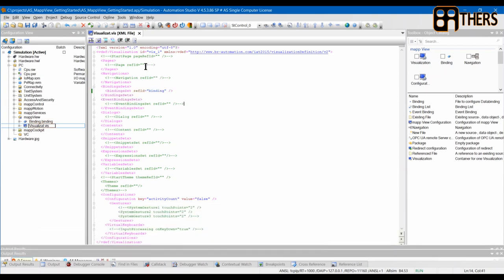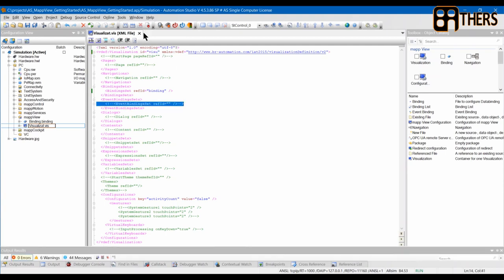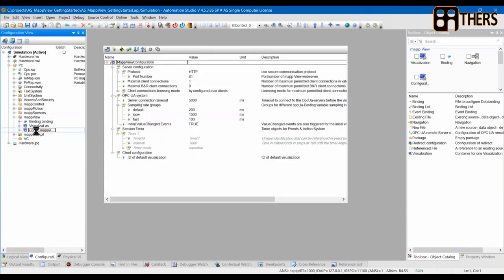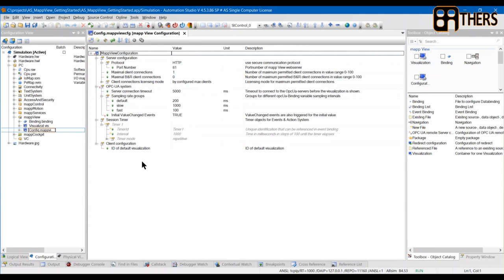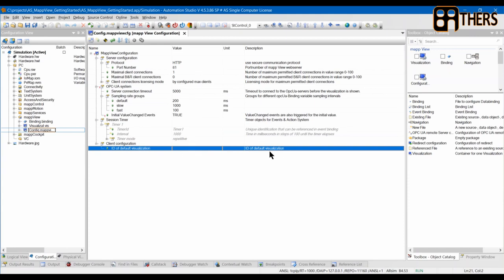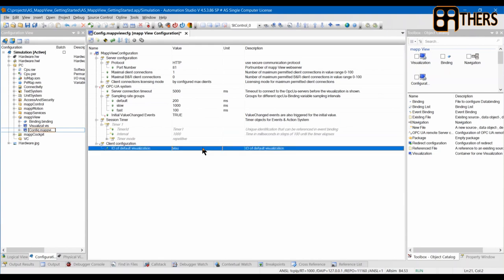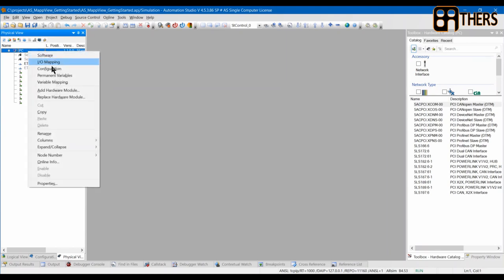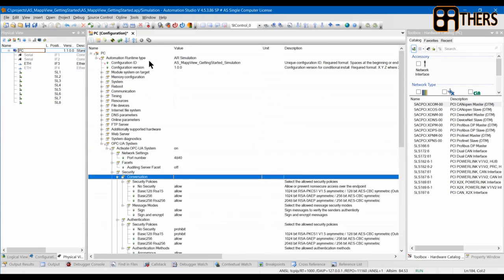This is where we add pages later, so I'll rename it to 'misu'. Copy the name, close it, then add Map View Configuration and go into Config. This is where you configure your Map View information — you can set the port number to 81, which is the default. The default ID will be 'misu'. Then we go into Physical View, right-click on your PLC, go into Configuration, OPC UA, and activate OPC UA. That's all we need to do here.